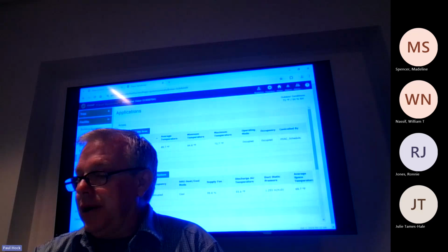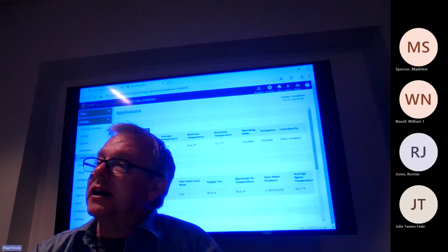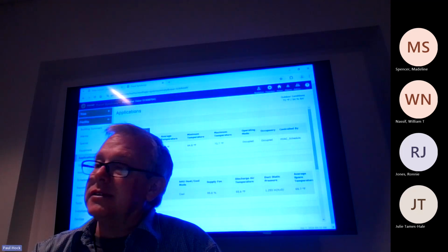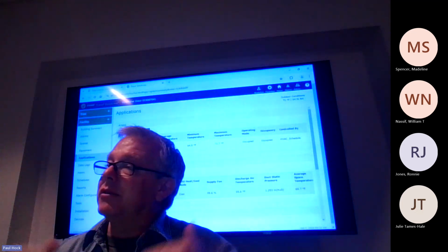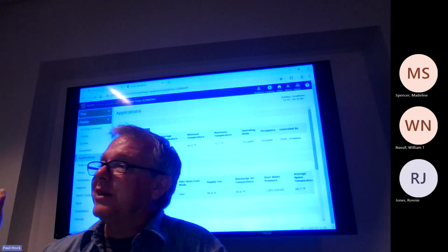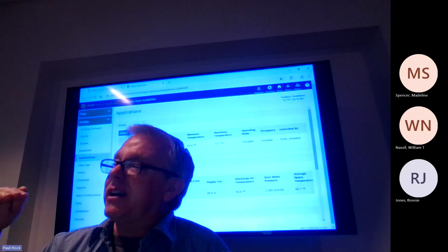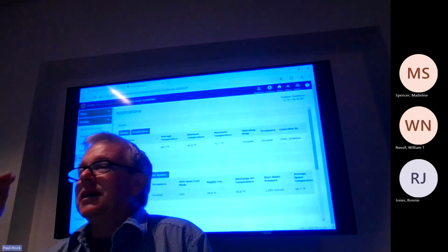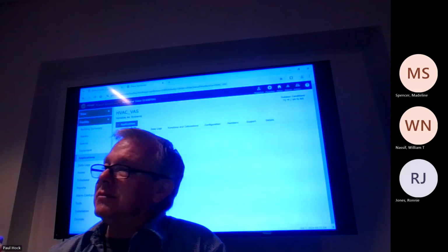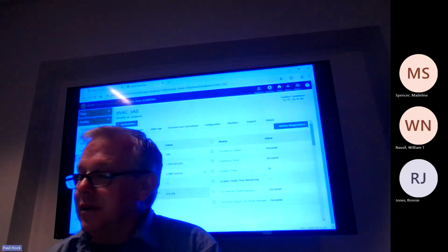And then there's what we call a variable air system. This is what controls your duct static on the air handler. So the VAS is looking at all your VAV boxes. It's looking at your valve positions and your airflow. So basically, if we got a box that's not maintaining, it's going to start speeding the fan up. It wants to get that box maintained. If everything's in heat mode, minimum speed, it's going to start slowing the fan down. Don't need to run 100% if everything's at minimum, right?